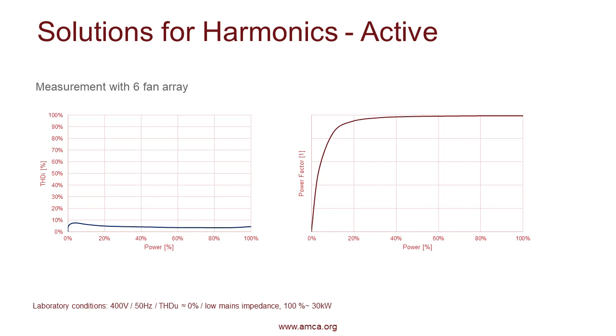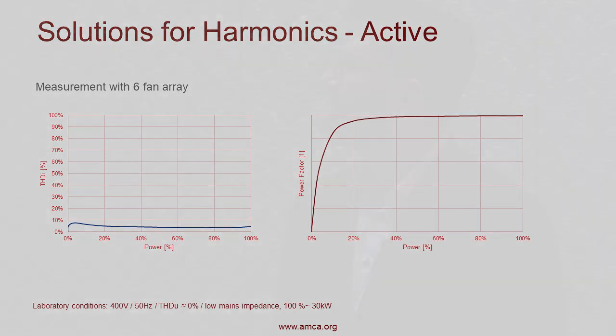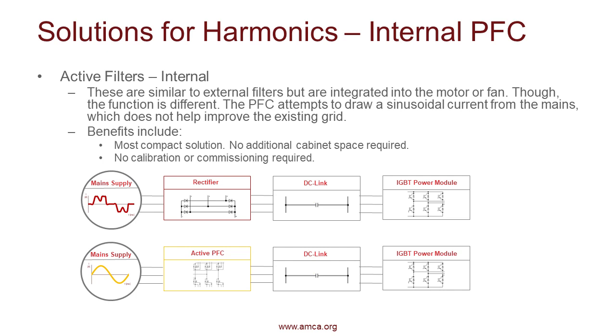We can look at that closer here. So we're actually reducing the total harmonic distortion current to less than 10% for the entire power percentage. And for a majority of the power percentage, you're seeing that that power factor is close to the 1. So this is increasing your efficiency and saving you money. And now we can look at an internal PFC, power factor correction.